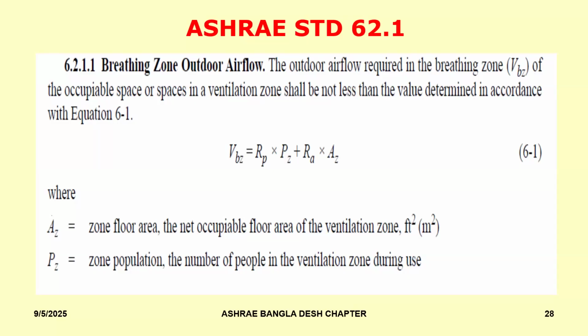And 62.1 gives you two options. It doesn't really talk about air changes per se. But what it says is, how is the pollution in the space caused? It's caused on account of two factors. One is the people themselves, and the other is the space itself. The space will comprise various things, like we talked about earlier, things like furnishing and laminates and carpets and so on and so forth.